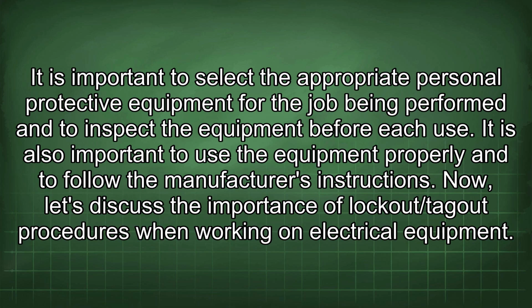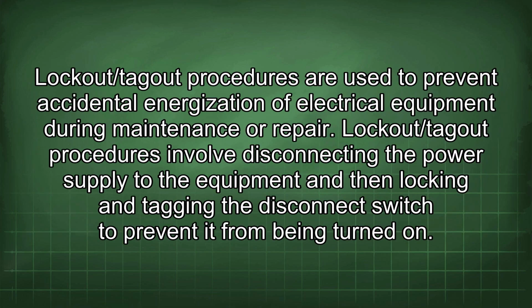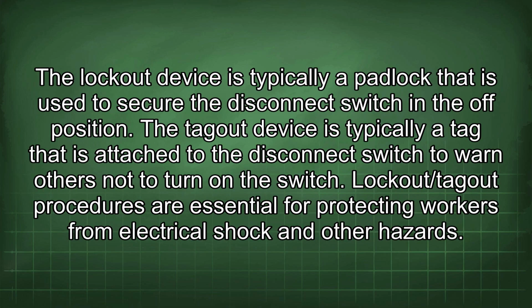Now, let's discuss the importance of lockout/tagout procedures when working on electrical equipment. Lockout/tagout procedures are used to prevent accidental energization of electrical equipment during maintenance or repair. Lockout/tagout procedures involve disconnecting the power supply to the equipment and then locking and tagging the disconnect switch to prevent it from being turned on. The lockout device is typically a padlock that is used to secure the disconnect switch in the off position. The tagout device is typically a tag that is attached to the disconnect switch to warn others not to turn on the switch.